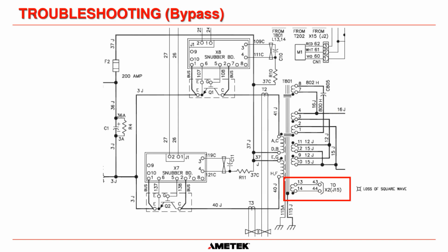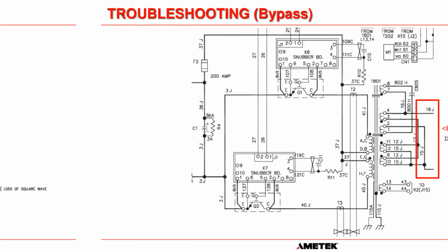And basically, this goes up to the X2J15 board, and you should have basically a square wave going in there. You can measure it with a scope, but if you measure it just with the Fluke, it should be anywhere between 14 to 18 volts AC. If you don't have 14 to 18 volts there, then there's either something wrong with that transformer, which you'd have to get the whole transformer replaced. But usually if you follow this up to X2J15, there could be a break in the wire going all the way up to the control board. And if that's the case, you need to figure out where the wire is broken, or if there's a bad connection at the control board itself.